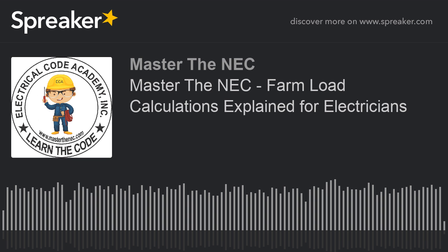So let's say of that 385 amps, we looked at it and we determined that at any given time, the loads that are expected to operate simultaneously add up to, say, 65 amps. So I might have a conveyor running and a blower running, and I've looked at the way these things work. You're doing a calculation, right? You have to ask questions. You need to tell me which loads are going to operate simultaneously. And then you add those loads up. And in our case, we say it was 65 amps.